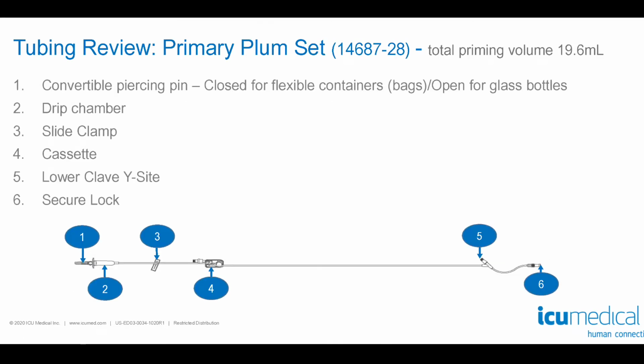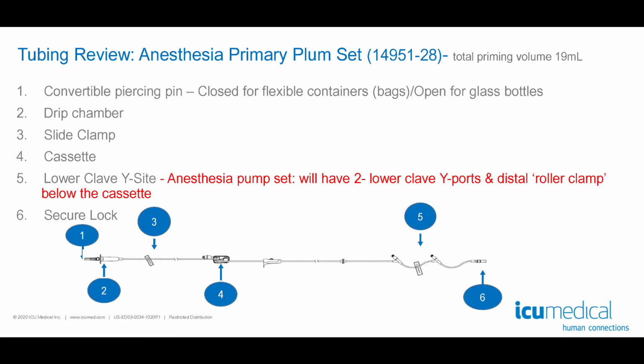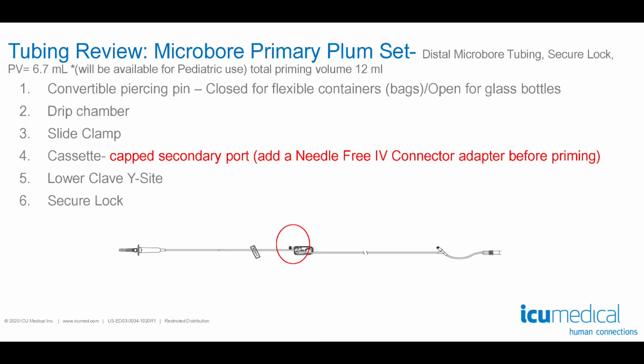This is our primary set with the Plum 360 that most of you will use. You will get a chance to prime this set later on. This will be our main anesthesia set. Please note that the anesthesia set will have 2 lower clave Y ports and a distal roller clamp, in addition to a back check valve. We will also have microbore tubing.